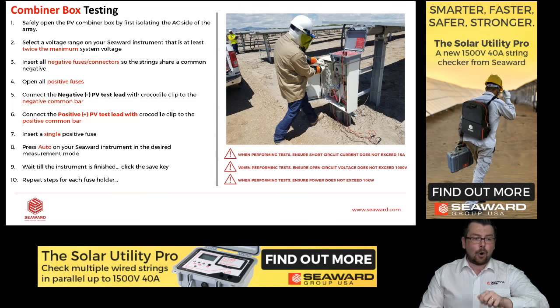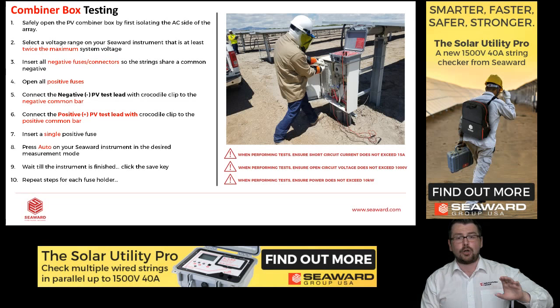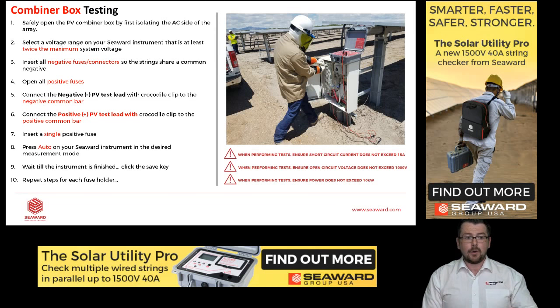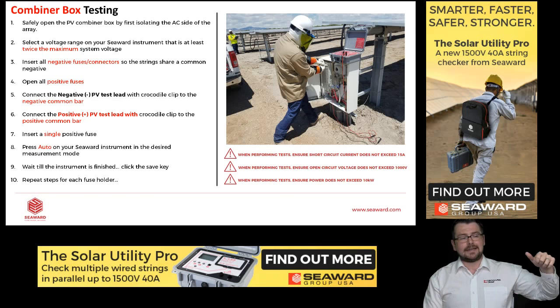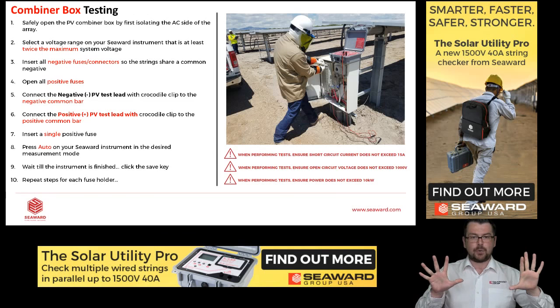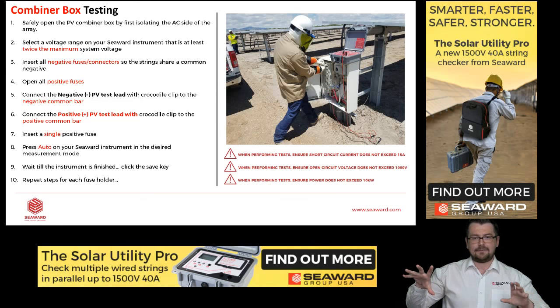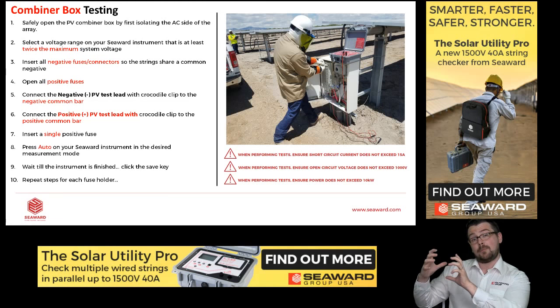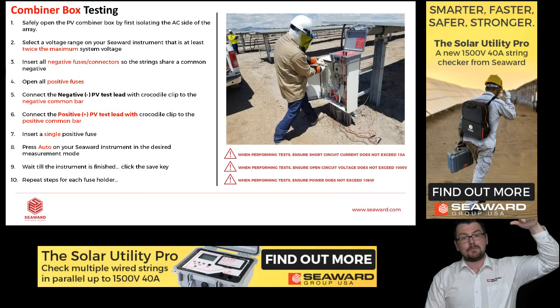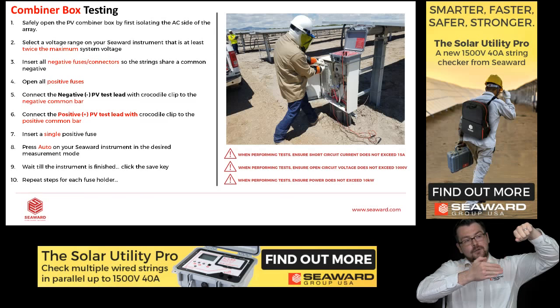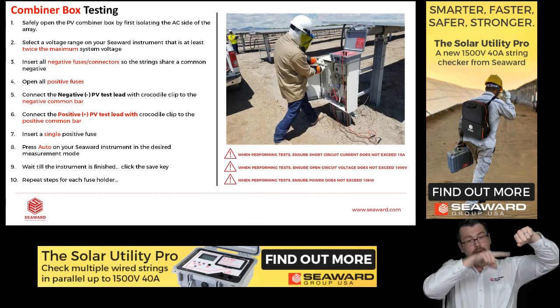First of all, safely open the combiner box and isolate the AC side of the array if you can. Select the correct voltage on your instrument and then insert all of the negative fuses if you have them. We also want to connect to the common negative bar. We want to open up all of the positive fuses, so those are all open, and connect to the common positive bar. So the situation right now is we're connected to the negative and all of the strings in the combiner box are sharing that common negative, and we're also connected to the common positive, but all of the fuses are open, so there is nothing flowing.